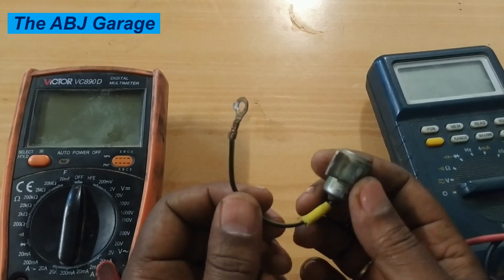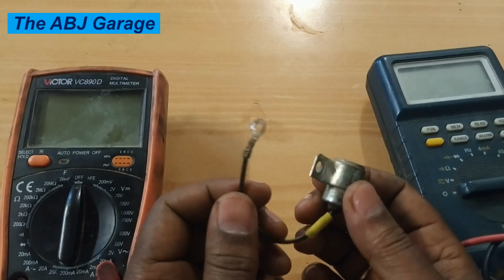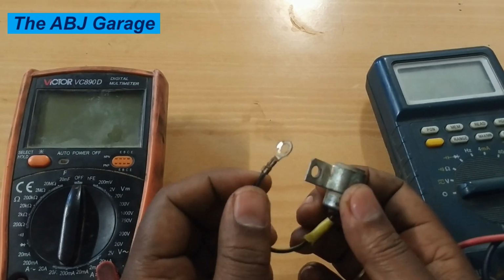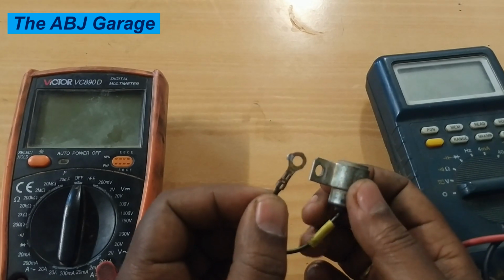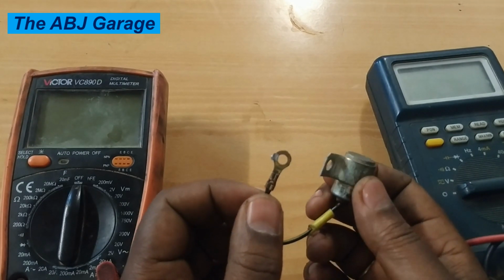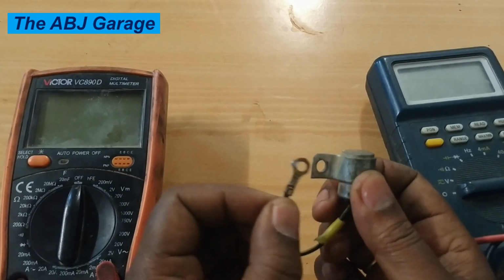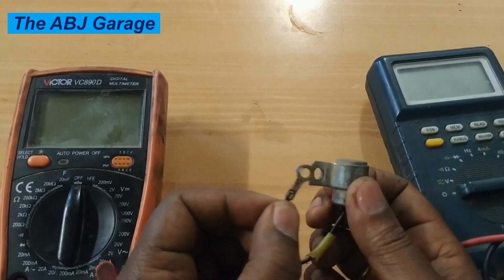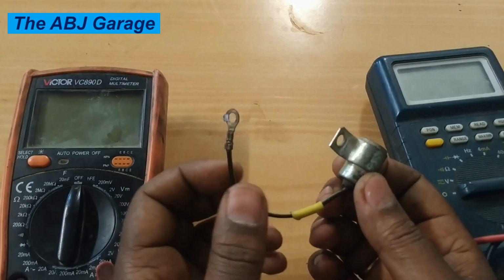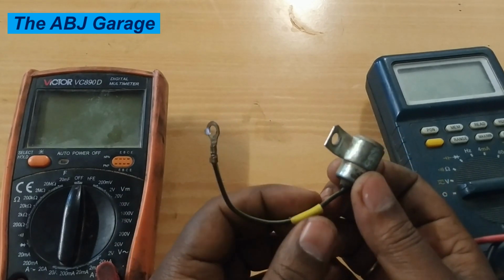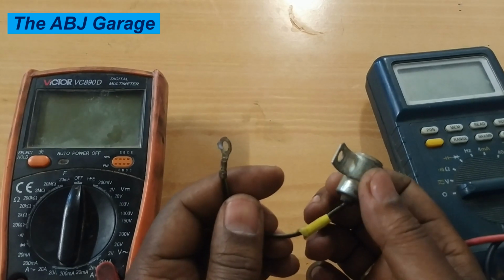Every time before starting any test on a capacitor, make sure that it is fully discharged. Fully discharging the capacitor is very essential in order to eliminate electric shock. That can be done by simply shorting out the positive to the ground. By shorting out, make sure that there is no charge, otherwise it will shock you if there is charge stored on the capacitor.